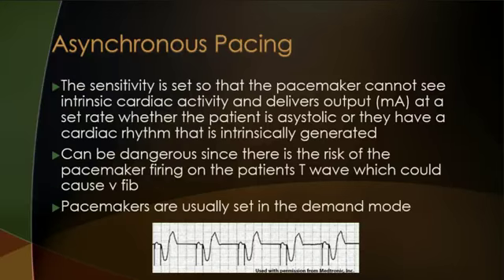Asynchronous pacing: the sensitivity is set so that the pacemaker cannot see intrinsic cardiac activity and delivers milliamps, or output, at a set rate, whether the patient is asystolic or has an intrinsically generated cardiac rhythm. This can be dangerous though, because the pacemaker may fire on T waves, which could cause the patient to go into V-fib. Pacemakers are almost always, I'd say 90% of the time, set in the demand mode.